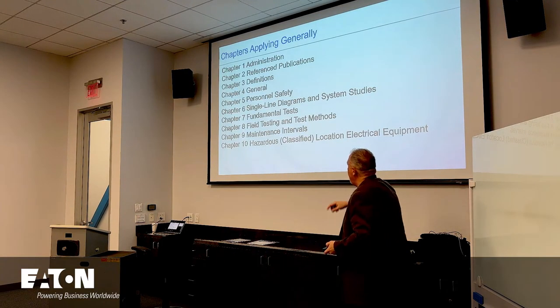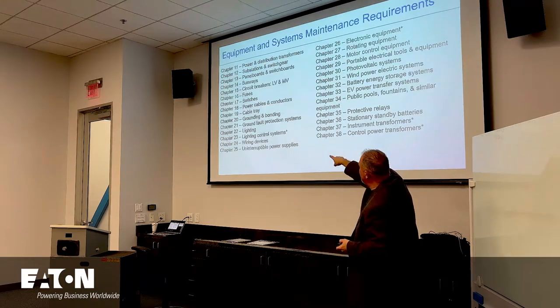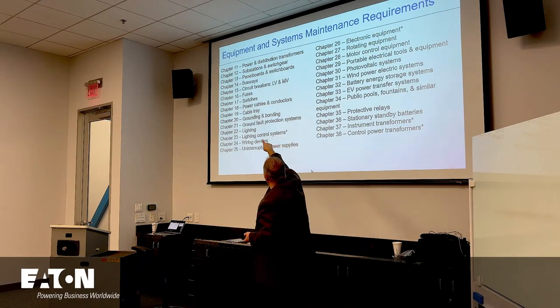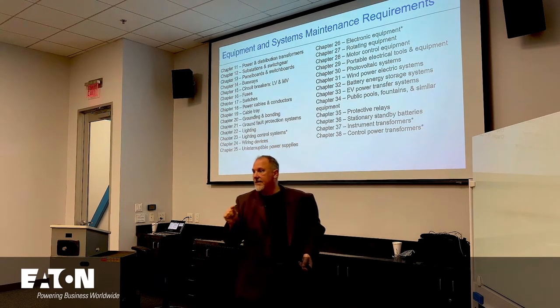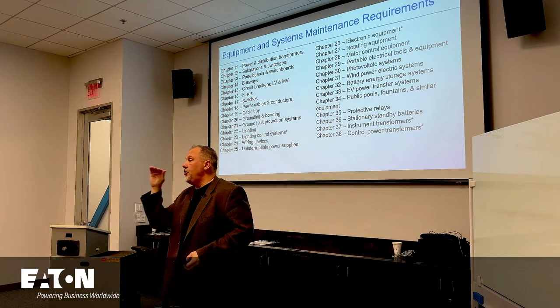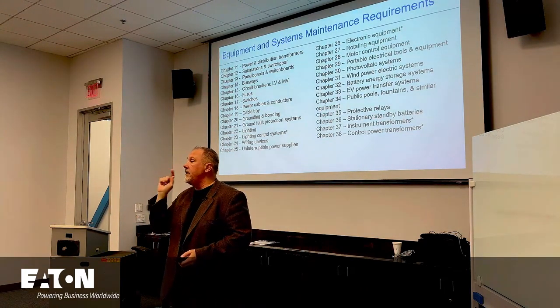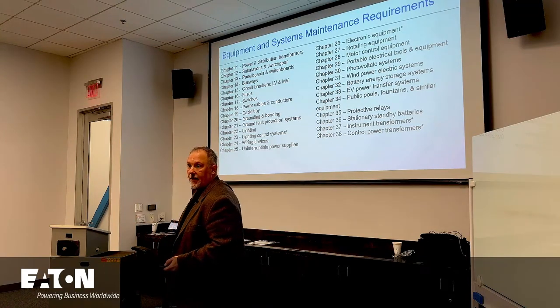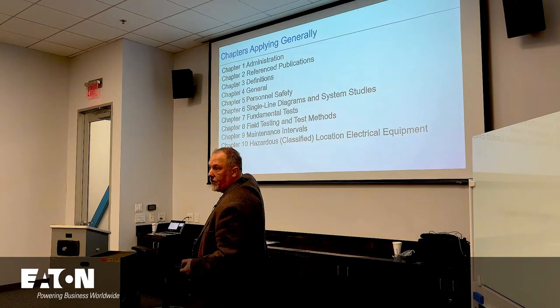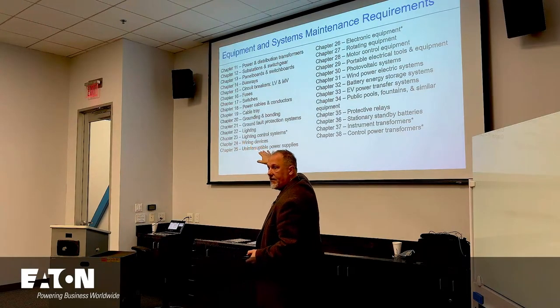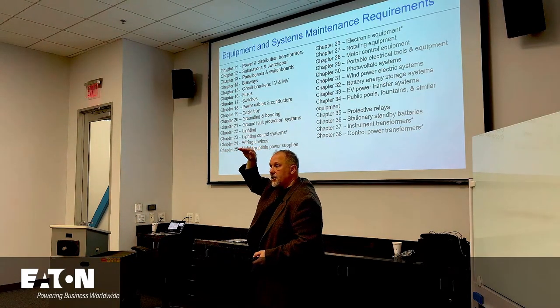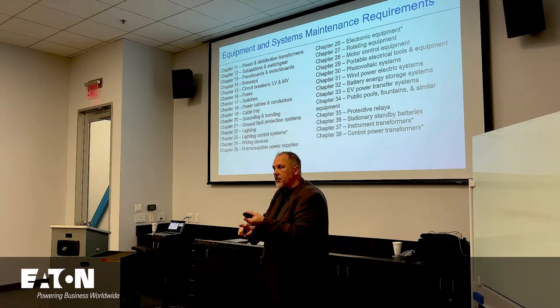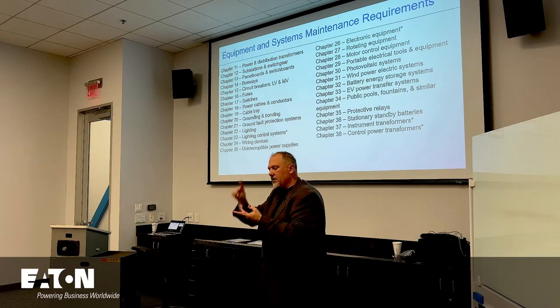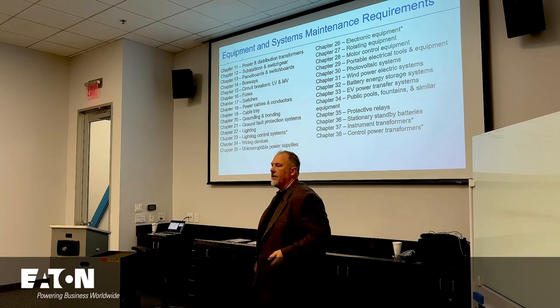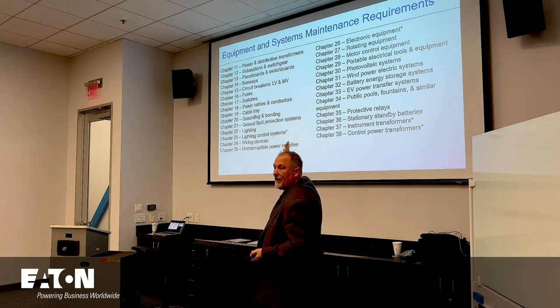I have them in here. And then you go to the chapter, say on fuses, chapter 16, and if chapter 16 says, hey, if you have this type of fuse, you need to do this more frequently, it can modify and change what's in chapter 9, maintenance intervals. So you would look at the individual components and just determine, it'll have a section for each of those: visual inspections, mechanical, electrical, and there's like two more. But in any case, each of those chapters tells you what to do for each of those products.